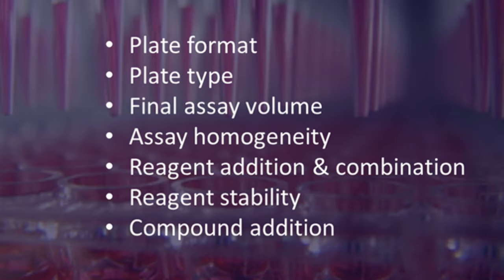Plate type. Assay plates can be black, white or transparent, and each is better for different assay types depending on the readout methods. For example, white plates are great for luminescence assays whilst black plates work well for fluorescence assays.